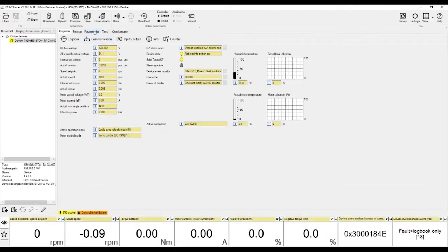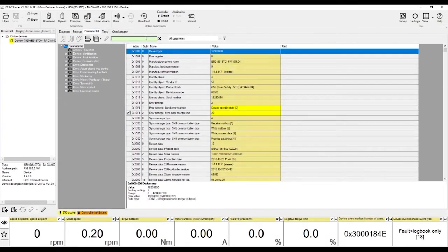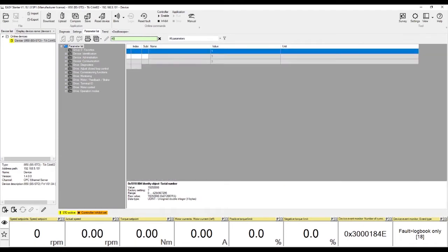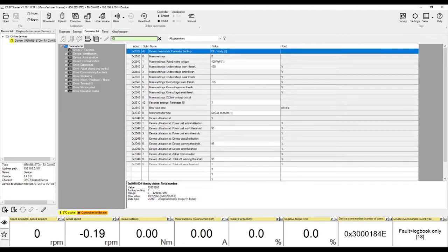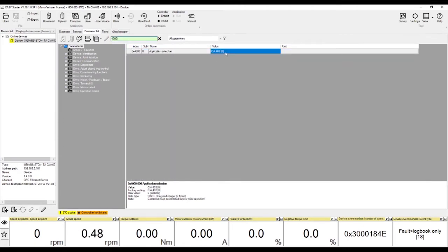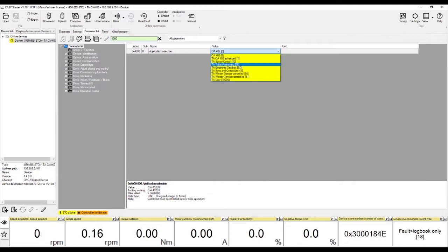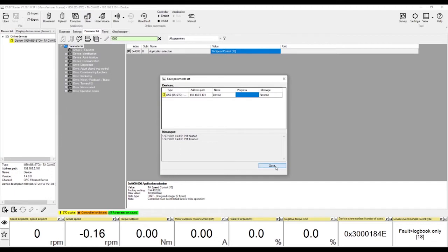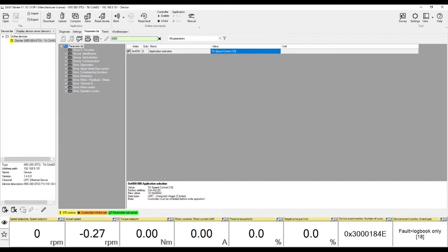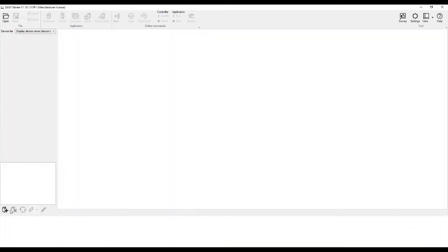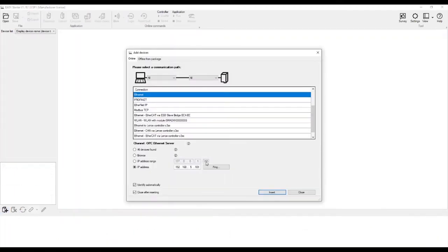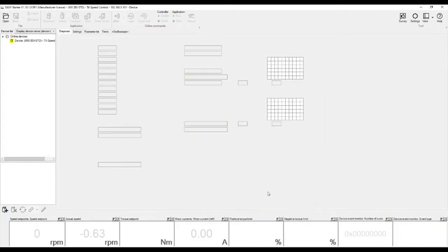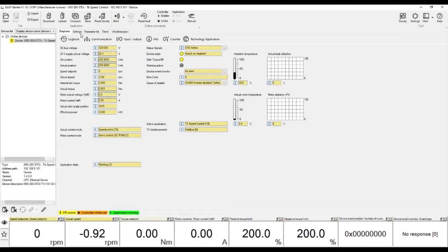Go to the Parameter List tab and type in 4000 in the search bar. This is the index code to select your application type. Click on TA Speed Control and save the value to your device. Remove the device and add it again. You'll see that the device name has changed in the device list to TA Speed Control.